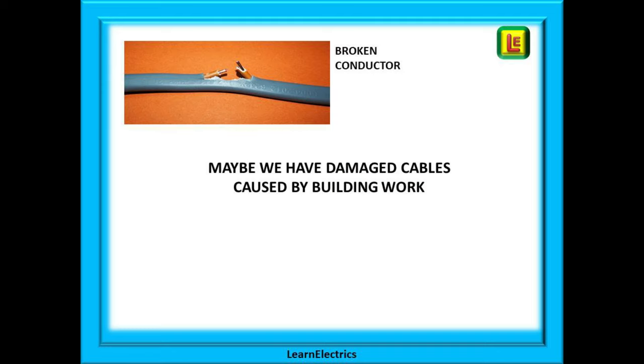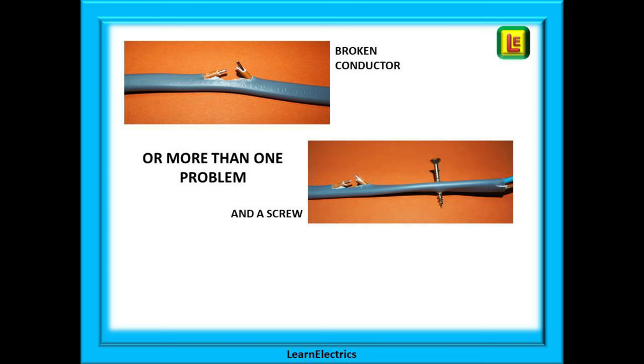Maybe we have damaged cables behind the wall caused by building work. Perhaps the cables have been cut when pulled through trunking systems. There are many ways that a cable can suffer damage and we may even have a cable that is damaged in two or more places. How are we going to find any of these problems before we energize the cables? It is infinitely better to find the problem during dead testing than to wait for it to go bang during live testing.